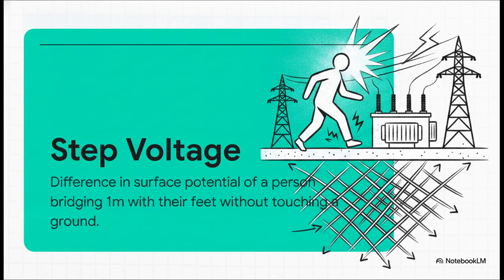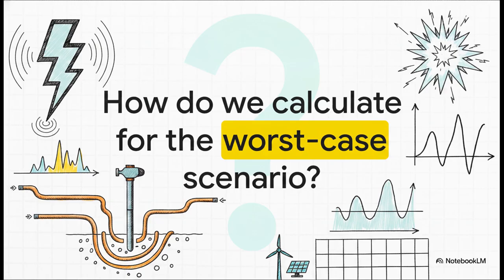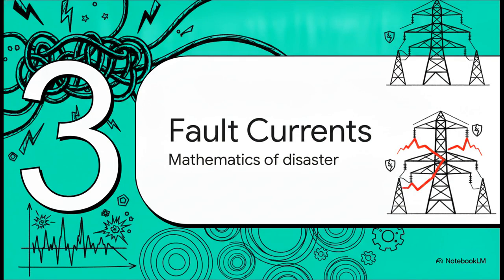That's exactly why these substations are built over massive, complex grids of buried bare copper to equalize that surface potential and keep everyone safe. So, it makes you wonder, right? How on earth do engineers calculate for the absolute worst-case scenario? How do they mathematically prepare for a direct lightning strike or a massive short circuit to ensure all that buried copper is actually going to be enough? That brings us to Section 3, Understanding Fault Currents, the literal mathematics of disaster.